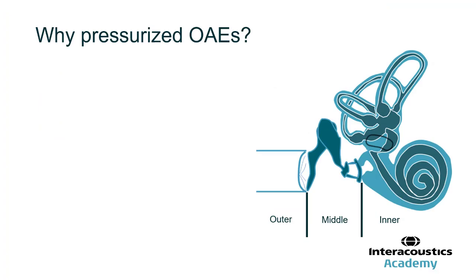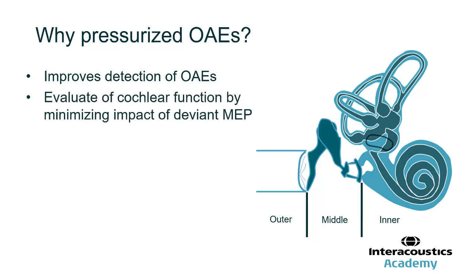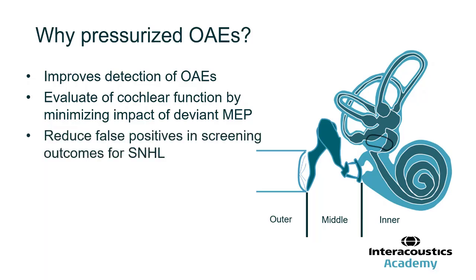I always like to start the talk with why, even though I haven't really presented any of the information yet. Hopefully I'll clear a lot of the information up during the talk. But why would we want to pressurize otoacoustic emissions? The first reason is that it improves the detection of OAEs, which I will show you in the coming slides. By improving the detection of OAEs, you're also able to evaluate cochlear function by minimizing the impact of deviant — meaning positive or negative — middle ear pressure, which stands to reduce false positives in screening outcomes for sensorineural hearing loss.